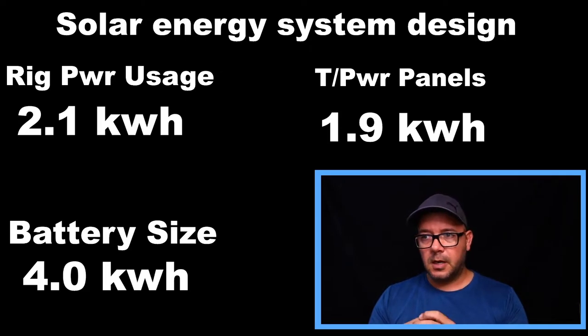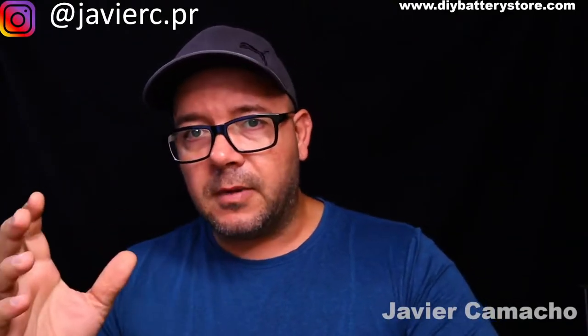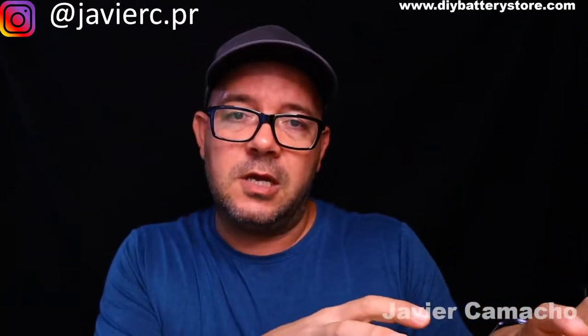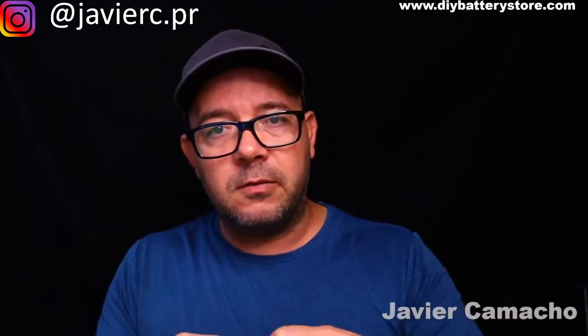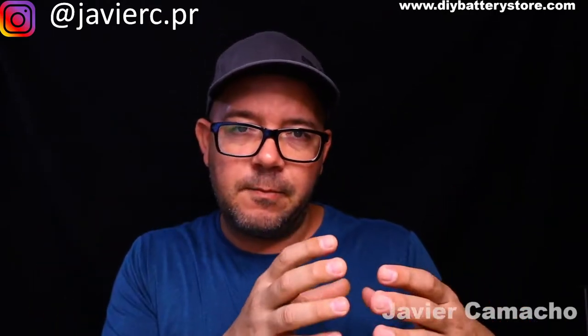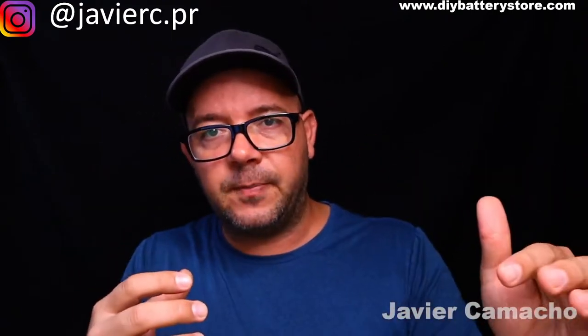Now, if this was an off-grid system, that would be more than enough, meaning that 1.9 kilowatts in panels would be more than enough to power the loads of the house and also recharge the battery. Now, every time someone talks to you about how to design a solar system, we have a formula. And that formula is based mostly on the battery size, but not that often based on the loads that you're going to use while you're charging your battery.